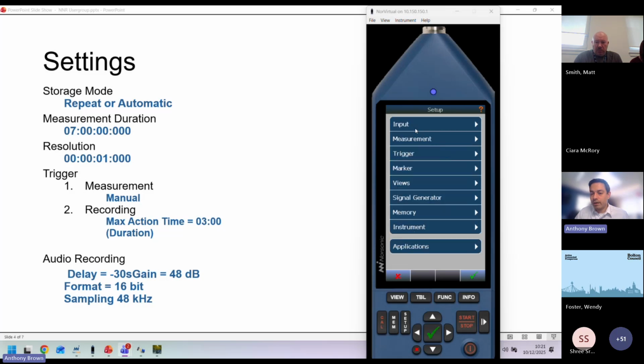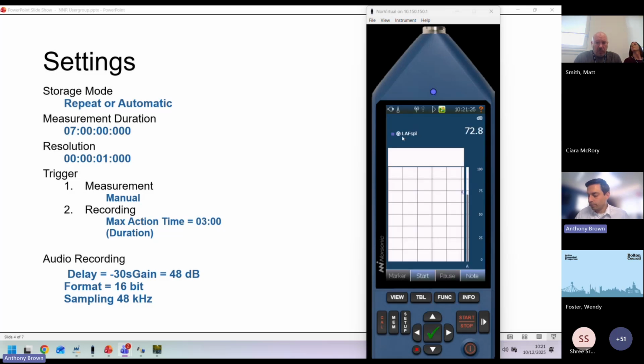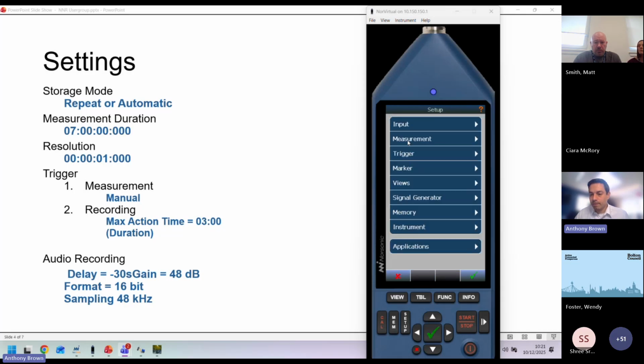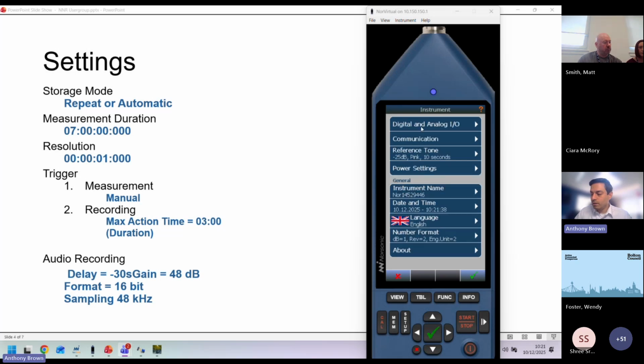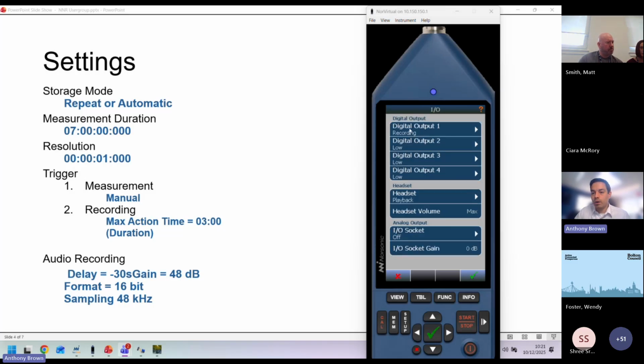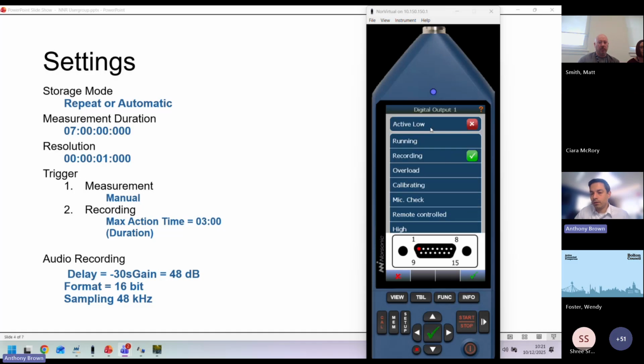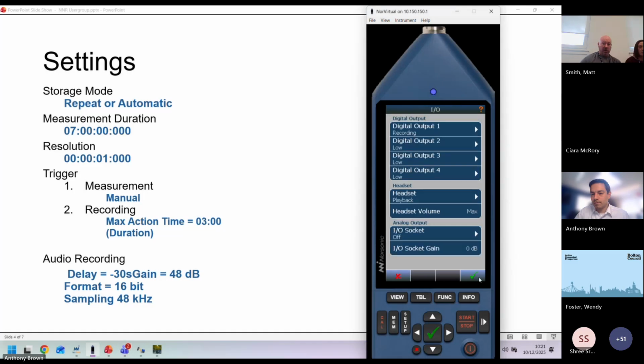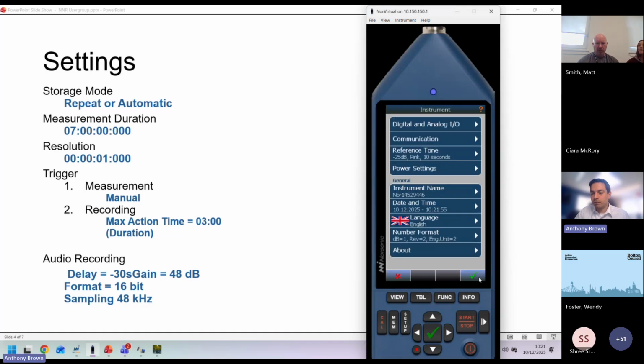I'm just going to show you again where those settings are in case anyone got lost. That was under setup, down to instrument, then digital and analog I/O, and then you set digital output 1 to recording - this one here - to recording. Once you're happy, press the tick keys to save this.